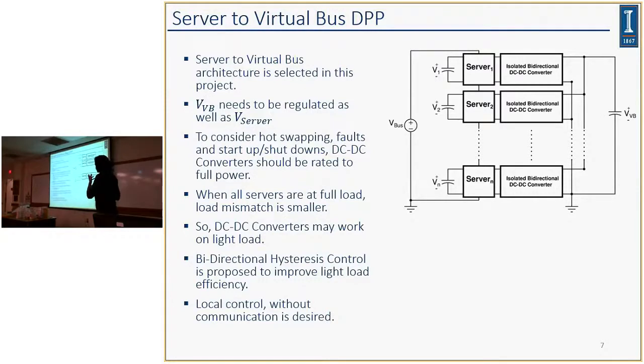So the main question is how do you rate these converters? Considering real data center operation, which sometimes requires swapping circuits or servers, or there may be faults or startup/shutdown issues, we rated these converters at full server power. However, as I told you before, these converters only need to process the difference power between the servers, so they need to be able to work efficiently at light load.